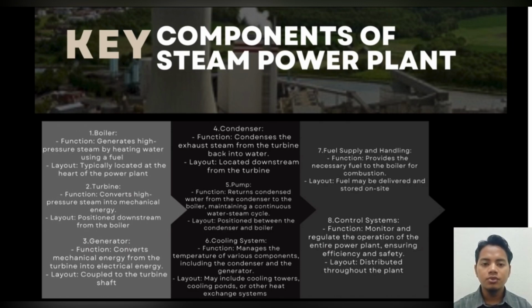Number 7 is fuel supply and handling. The function is to provide the necessary fuel to the boiler for combustion. The layout is fuel may be delivered and stored on site, then transported to the boiler as needed. Number 8, control system. The function of the control system is to monitor and regulate the operation of the entire power plant, ensuring efficiency and safety. The layout is distributed throughout the plant. The control system uses sensors and feedback mechanisms to manage the steam pressure, temperature, and other critical parameters.